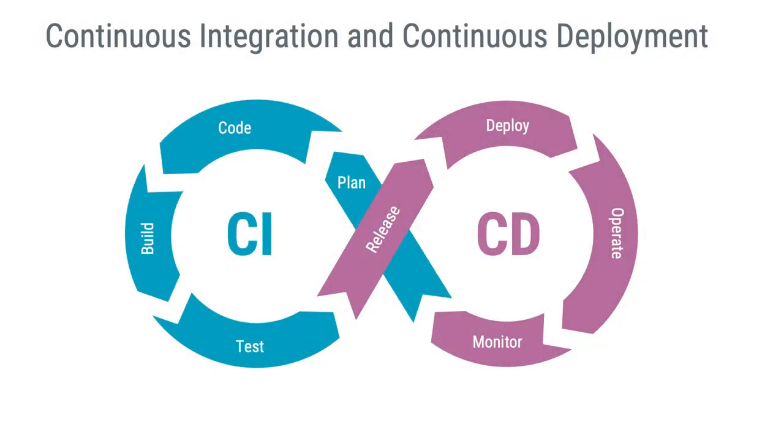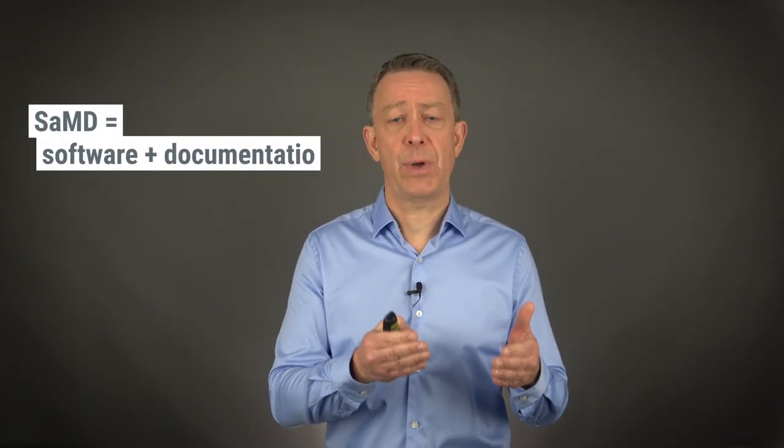Speaking of software release takes me to software release versus product release. In modern software development, it is common to find continuous integration and continuous deployment. Continuous delivery is a software development methodology where the release process is automated — every software change is automatically built, tested, and can be deployed to production at any time. This is cool, but before you get too excited, this is usually a software release and not a product release. When talking about software as a medical device, in an audit situation, I would expect to find accompanying documents such as the instruction for use and evidence of a successful design validation in your product release. You could say that a software as a medical device product is the combination of software and its relevant documentation.